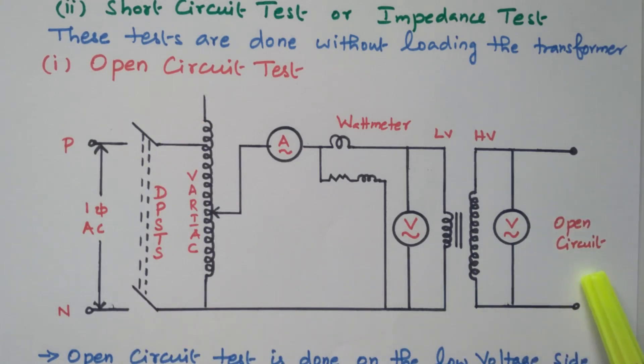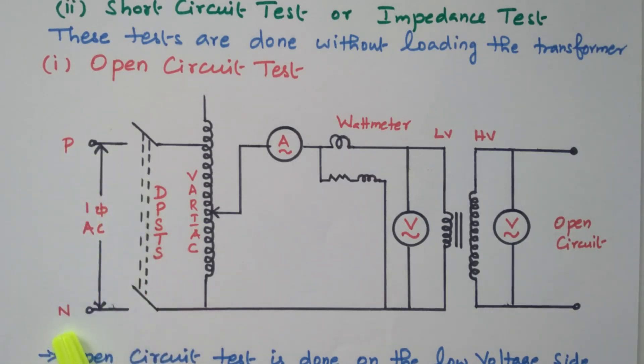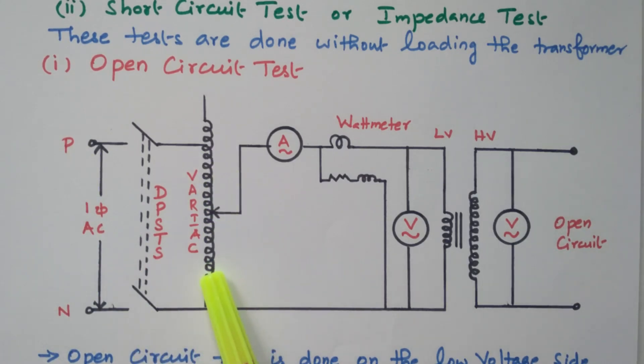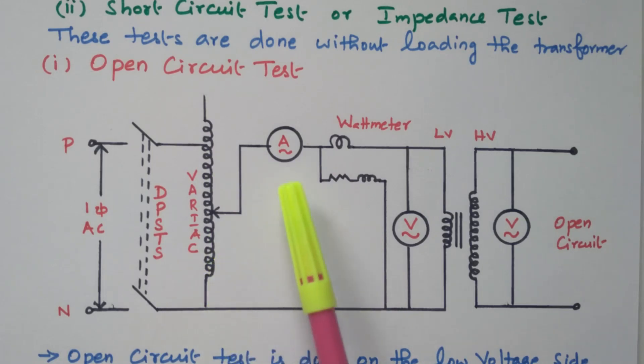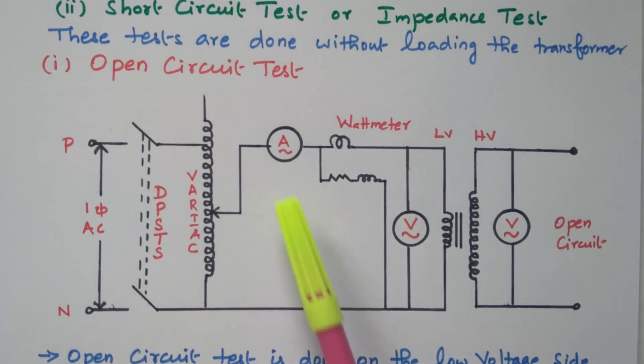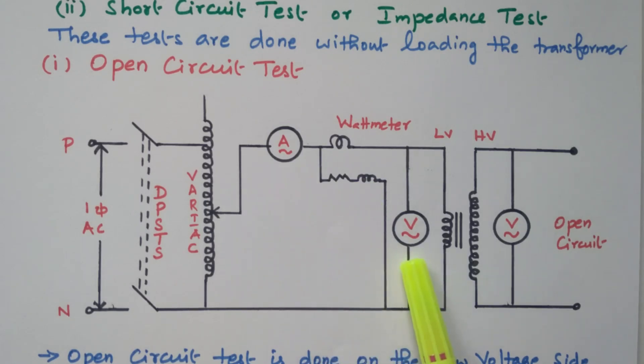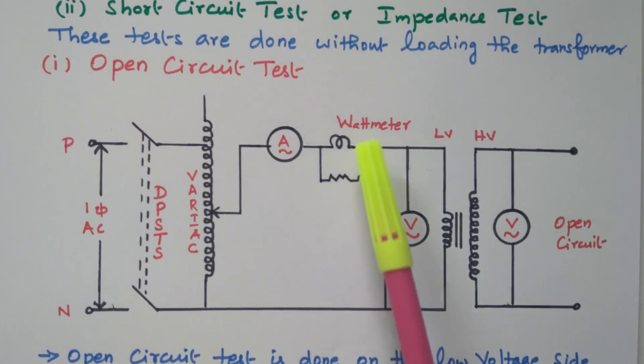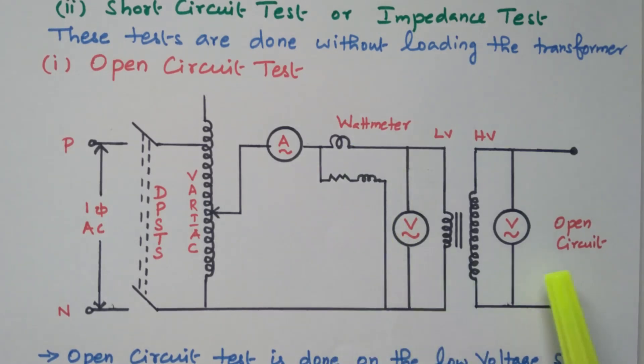All tests are performed on the low voltage winding in the open circuit test; the high voltage winding is kept open. A single phase supply — phase and neutral — is connected through a DPST switch. A variac is available to vary the input voltage given to the transformer; the variac is nothing but an auto transformer. Here we have an ammeter, wattmeter, and voltmeter. One more voltmeter is connected on the output side.